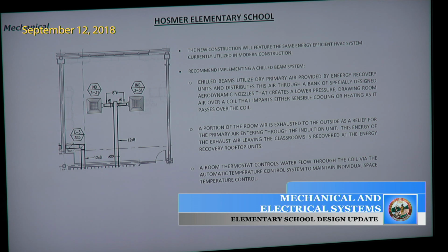Caveat, sorry guys, with chilled beam is condensation. Anytime I've ever used chilled beam, we've had major condensation issues where it's essentially raining inside. Especially with the temperature fluctuations we have in some of these classrooms and the humidity, I would really strongly be concerned about that.